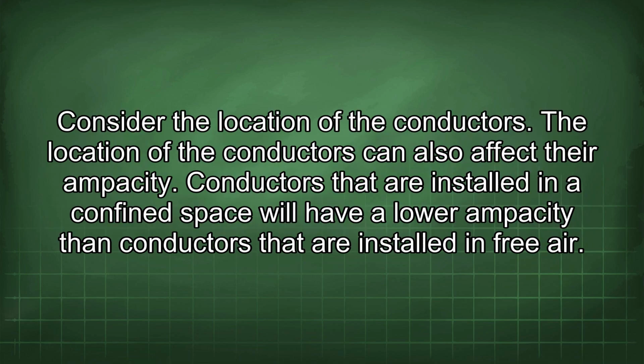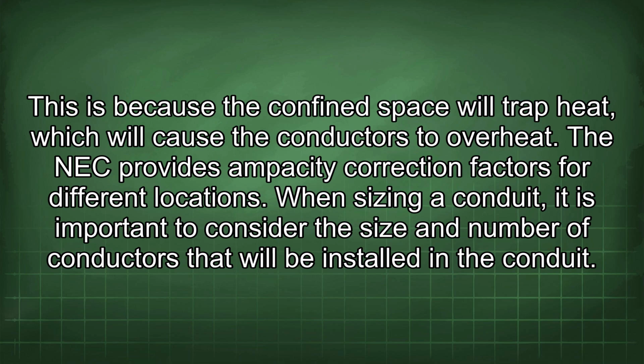Consider the location of the conductors. The location of the conductors can also affect their ampacity. Conductors that are installed in a confined space will have a lower ampacity than conductors that are installed in free air. This is because the confined space will trap heat, which will cause the conductors to overheat. The NEC provides ampacity correction factors for different locations.